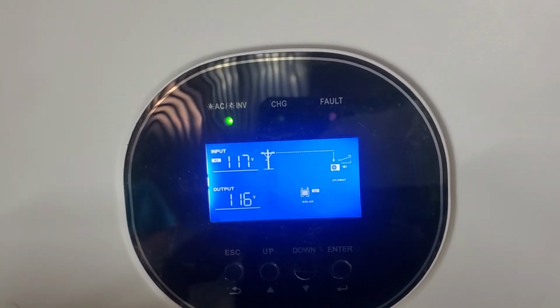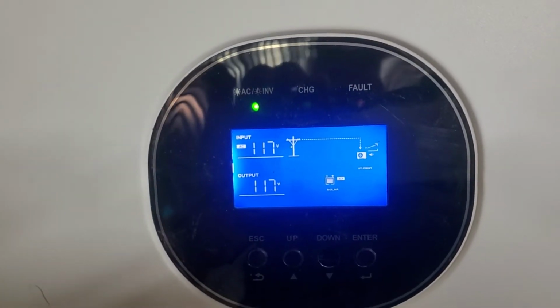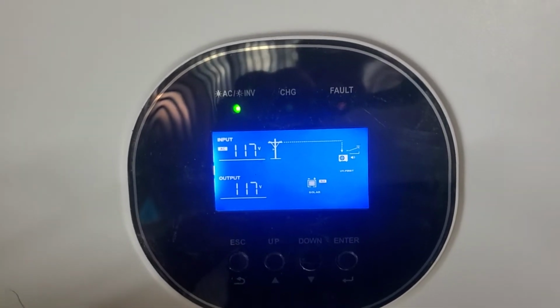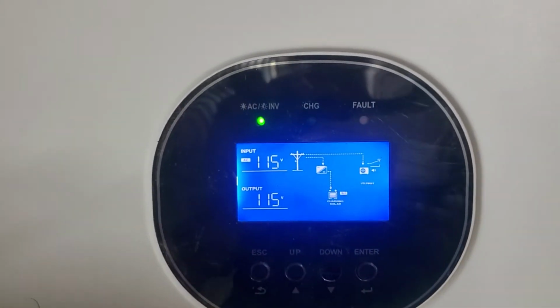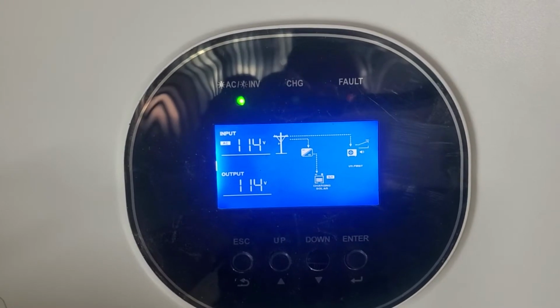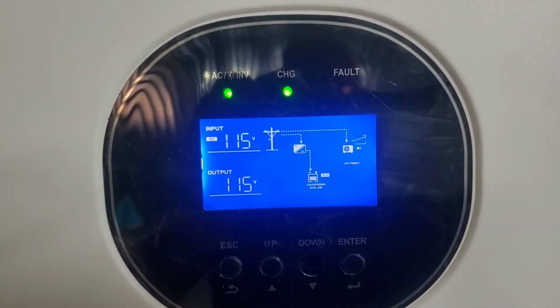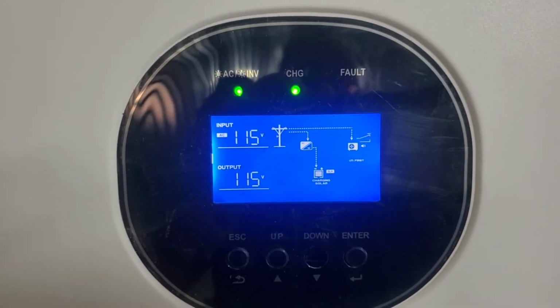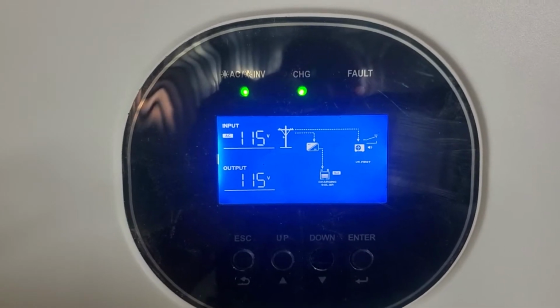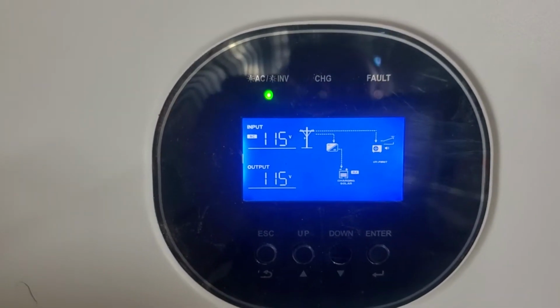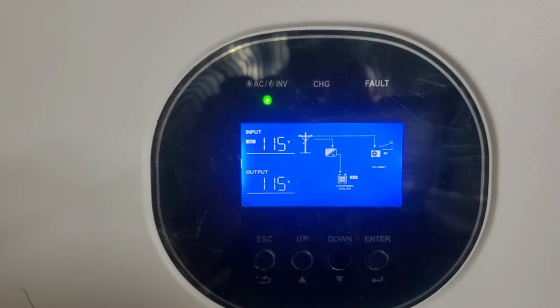You can see straight away it goes into bypass mode because it knows the battery is fully charged. But now I'm going to force it. It's going to try and charge that battery a little bit more. You see it's in utility mode, setting 01 set to UTL, which means that's the default. It's going to try and charge this battery even more. Okay, so utility.